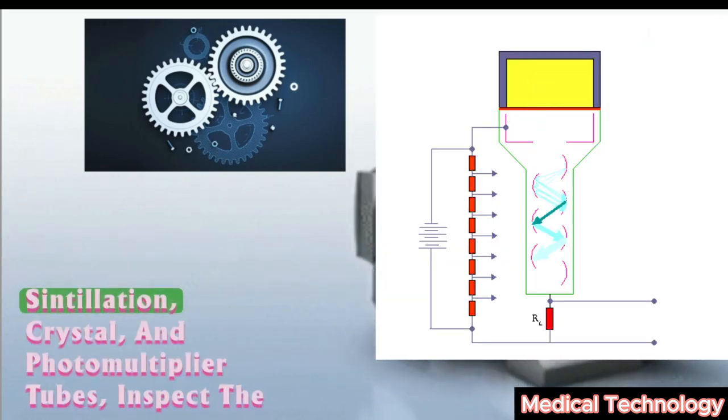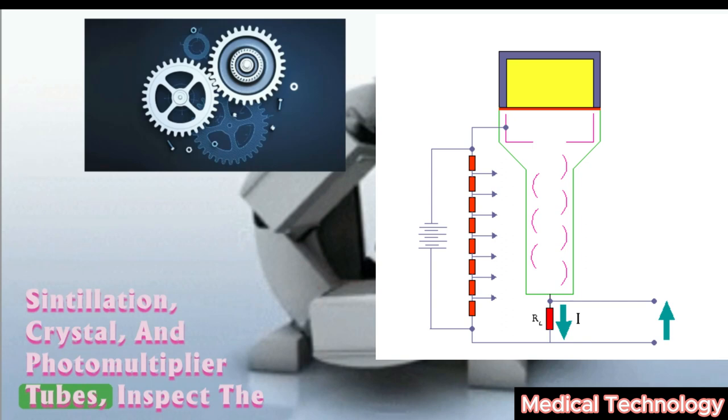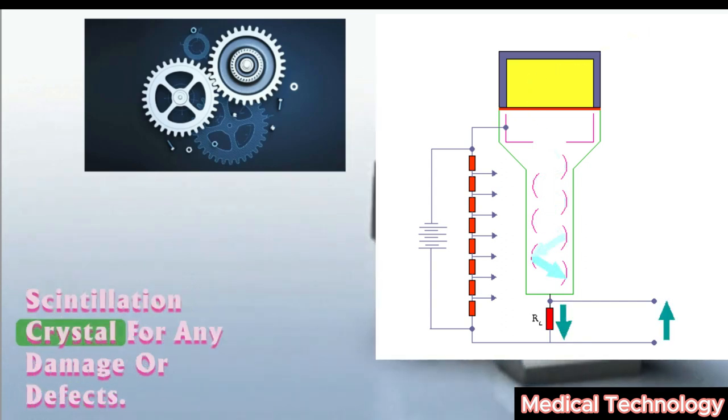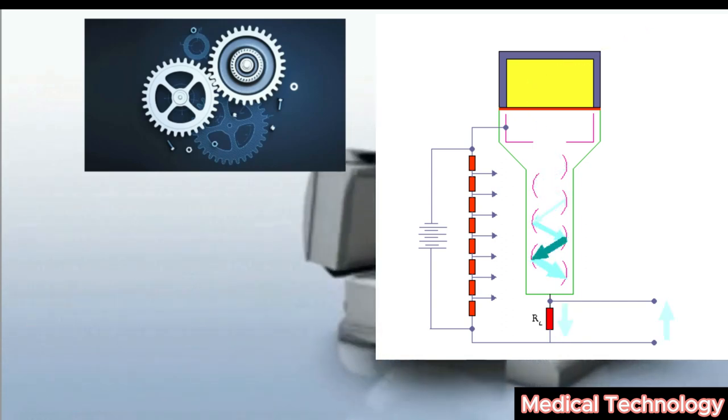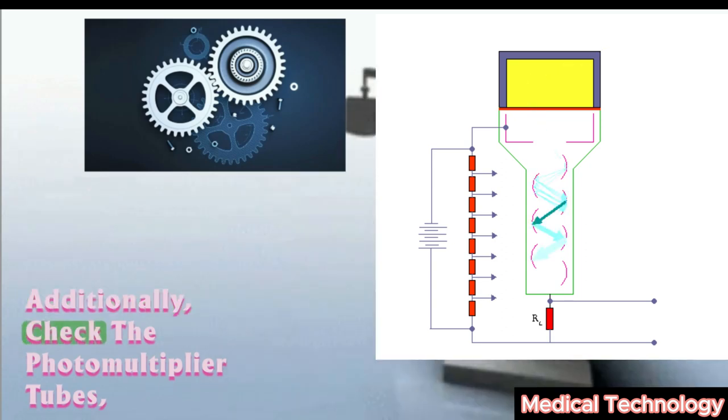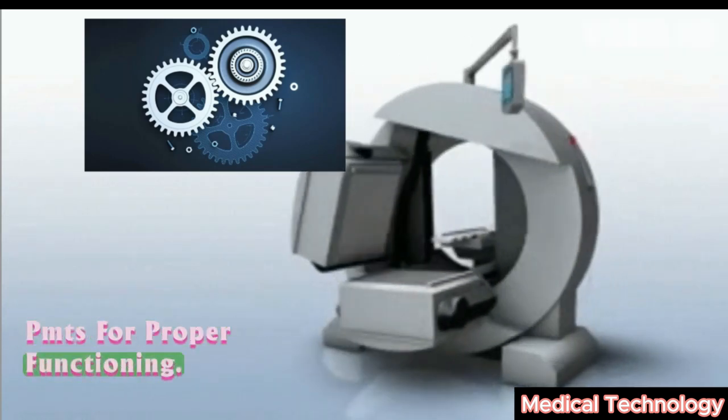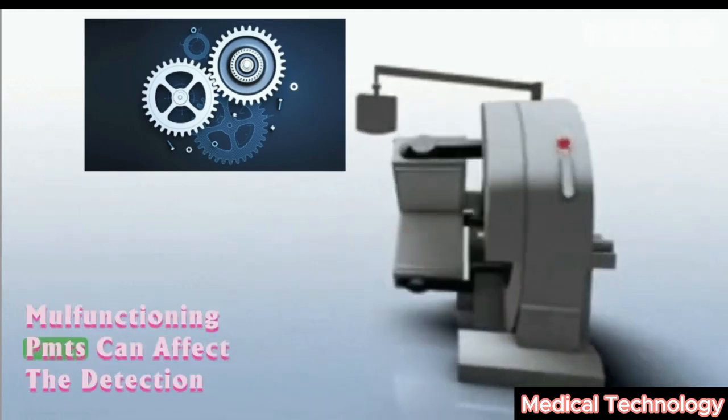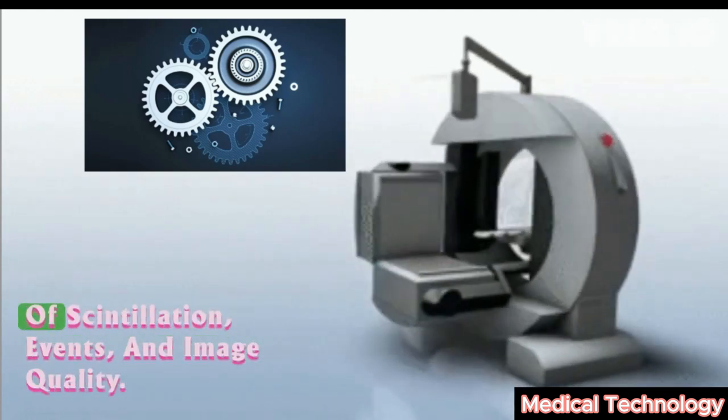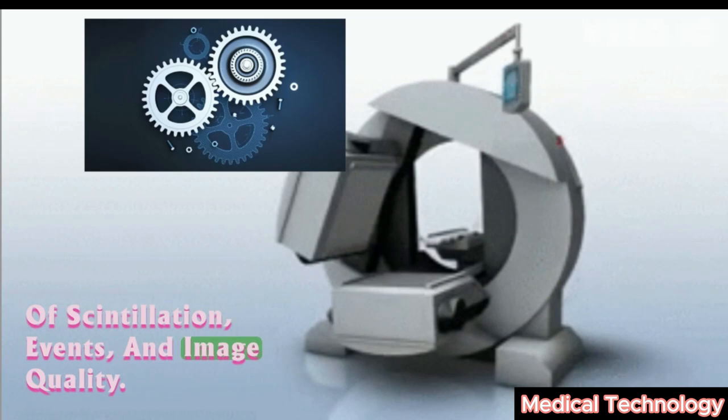Scintillation crystal and photomultiplier tubes: Inspect the scintillation crystal for any damage or defects. Additionally, check the photomultiplier tubes (PMTs) for proper functioning. Malfunctioning PMTs can affect the detection of scintillation events and image quality.